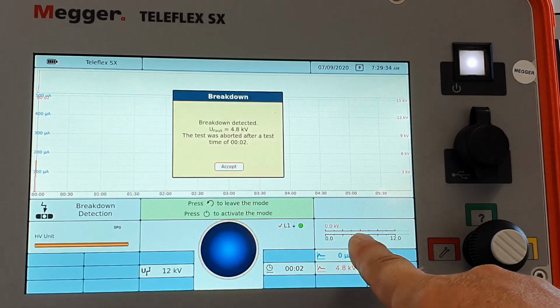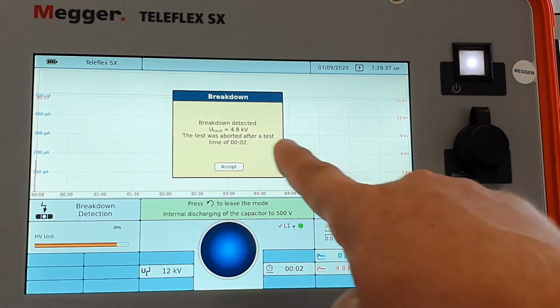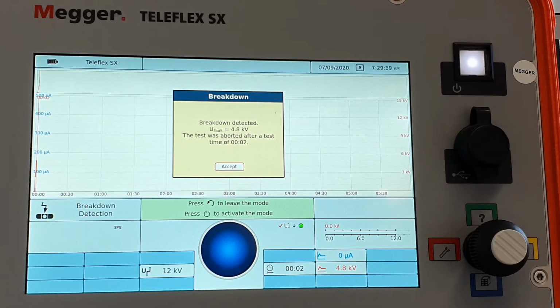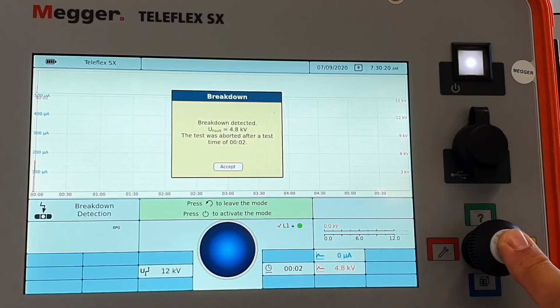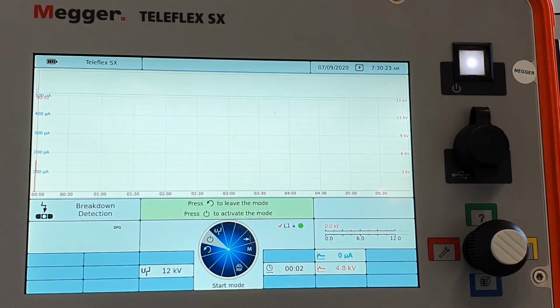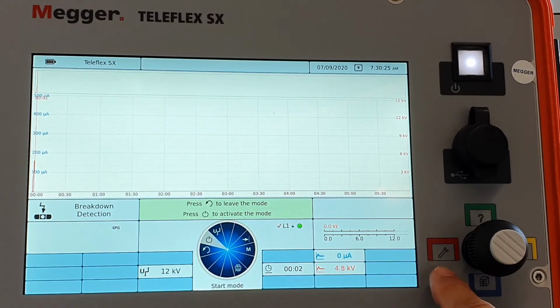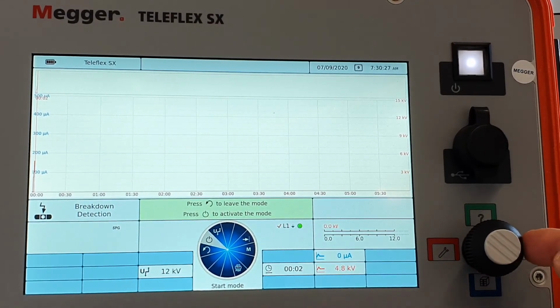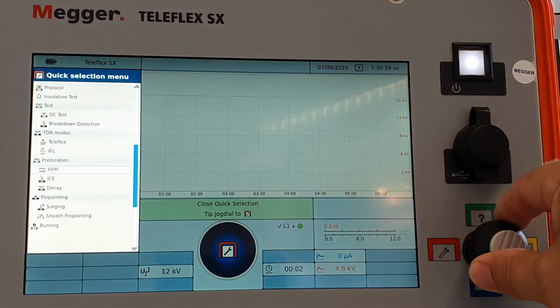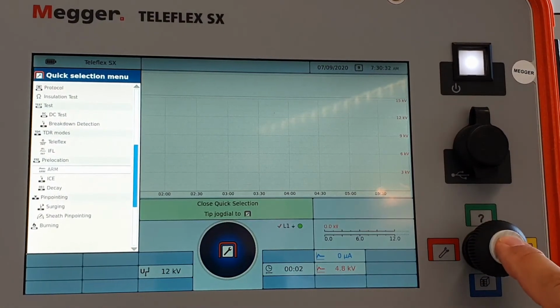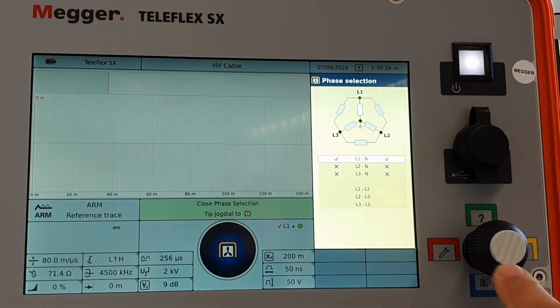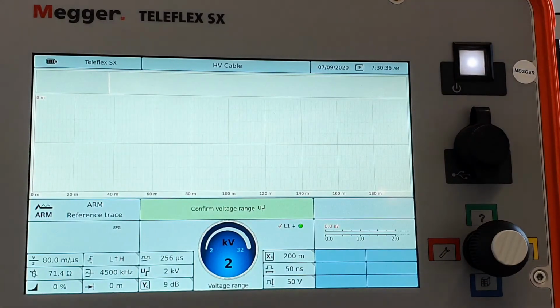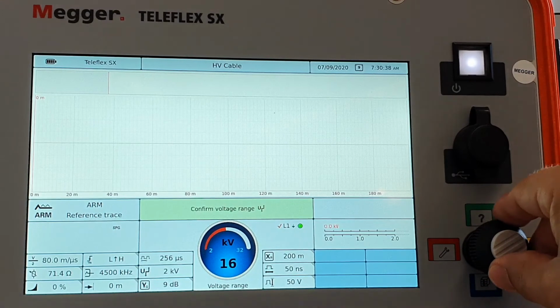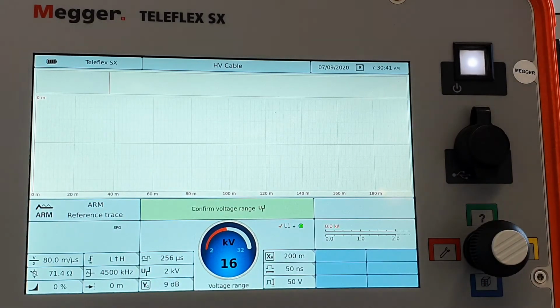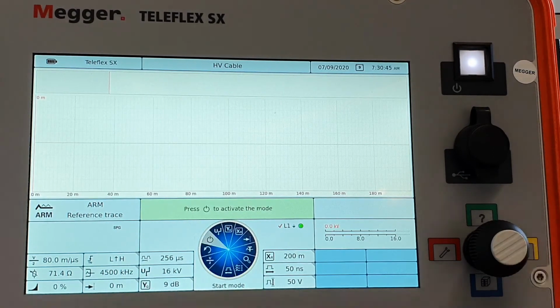I see my voltage building up, and I got a flash over at 4.8 kV. After confirming this message, I can now switch into the next mode. That would be arc reflection mode, finding the fault. Selecting the phase, yes, phase 1. I go into the 16 kV range because I do need more than 4 kV. I've just seen that. Confirm.